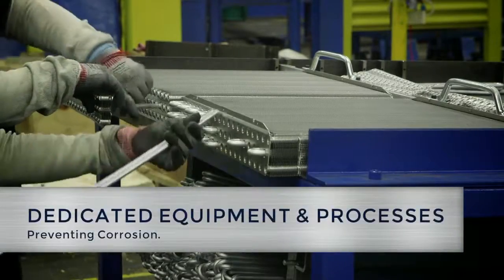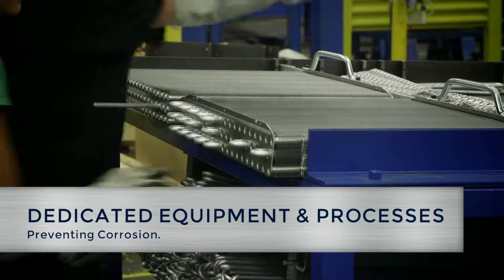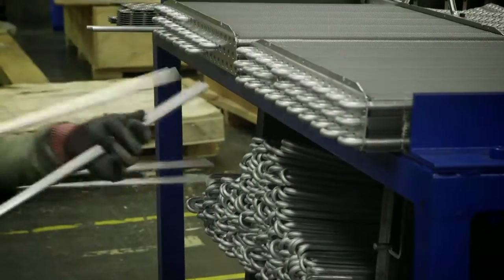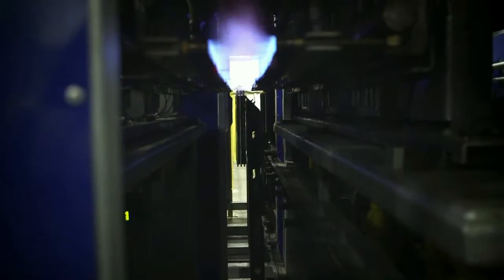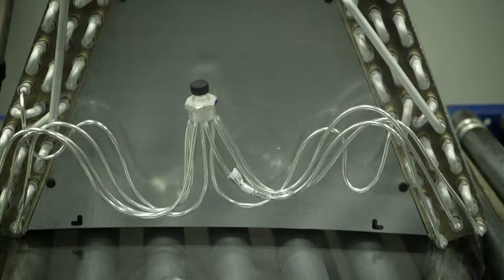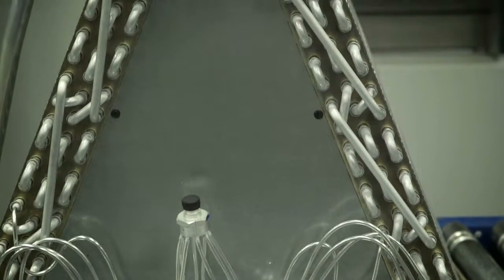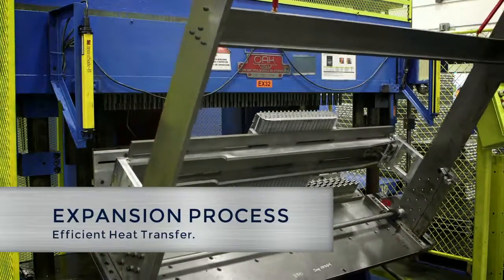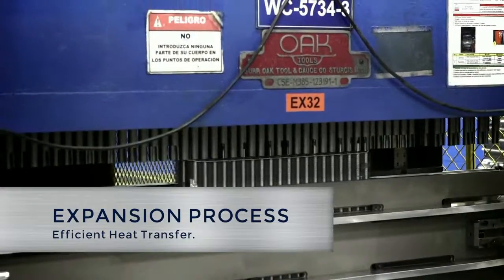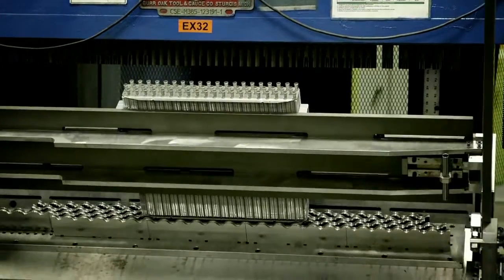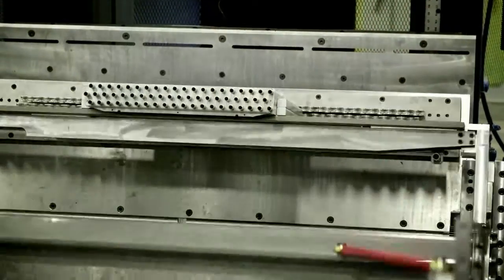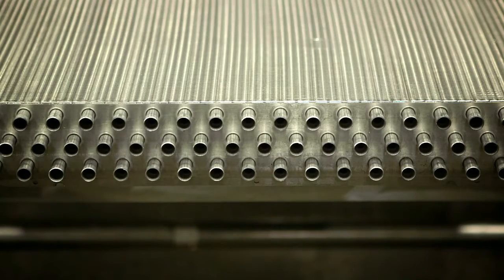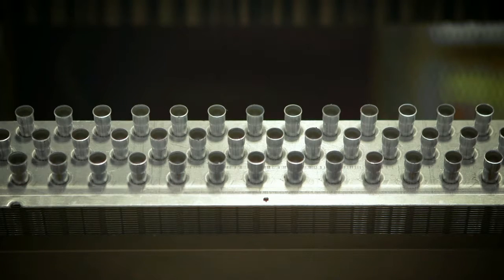During manufacturing, keeping copper particles from intimate contact with aluminum is critical in preventing corrosion. We employ dedicated equipment and processes that eliminate any copper to aluminum contamination to create a longer-lasting, more dependable coil. One of the steps in fabricating a coil is the expansion process, and this is where the tubing is expanded to contact the fin. Processing aluminum is uniquely different than other alloys such as copper. Aluminum oxide is very abrasive, and we employ a variety of different lubricants to allow the bullet to glide through the tubing and retain the internal geometry, the enhancements, to make efficient heat transfer possible.